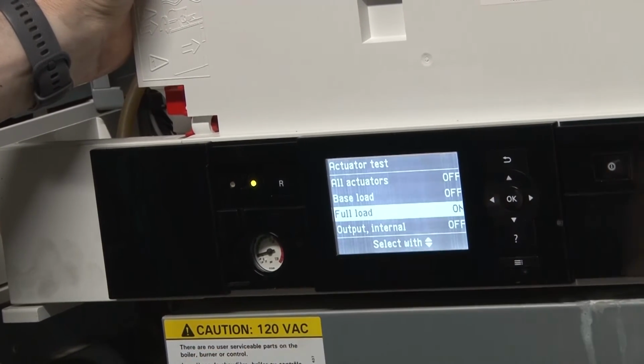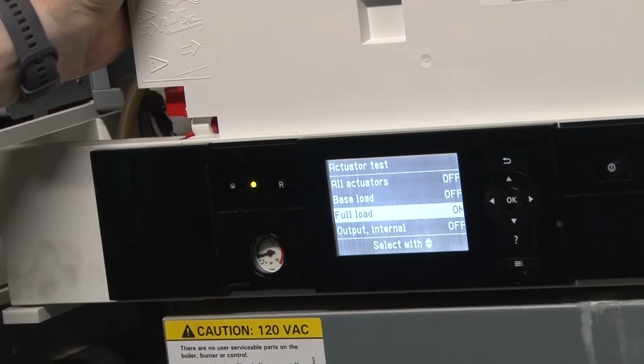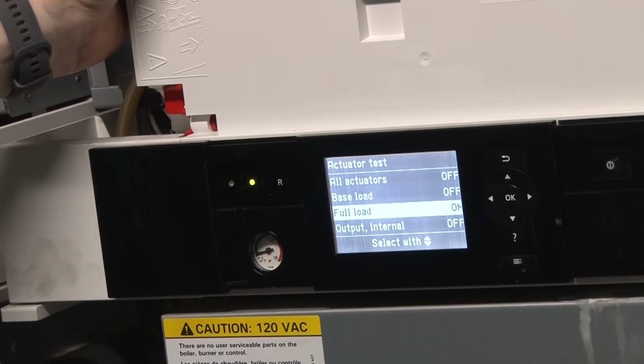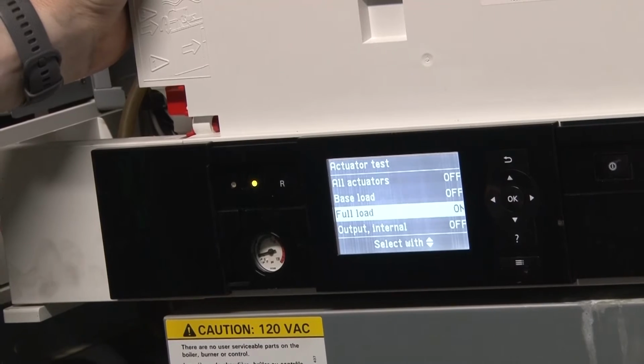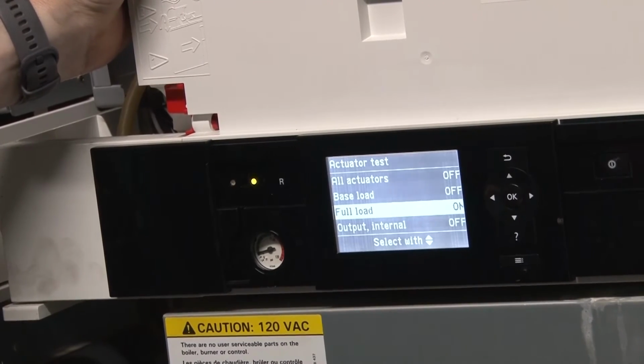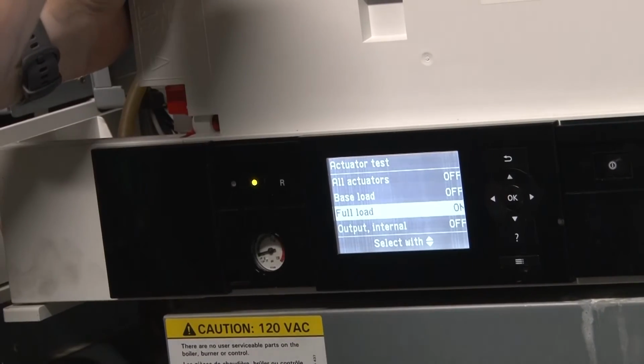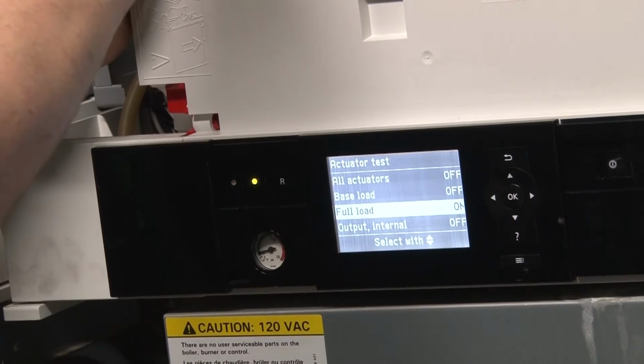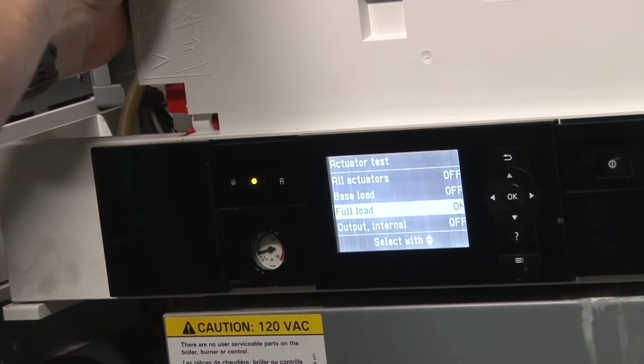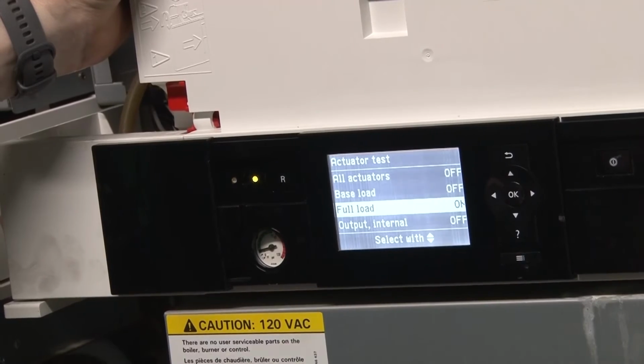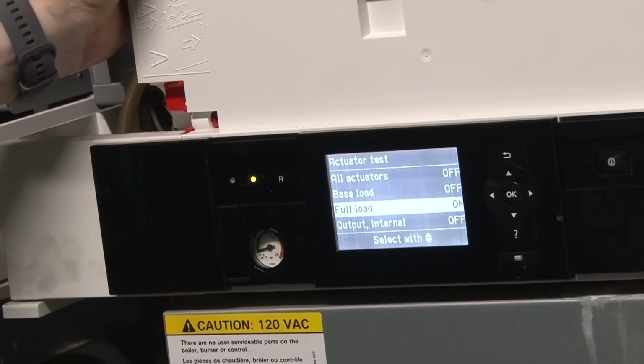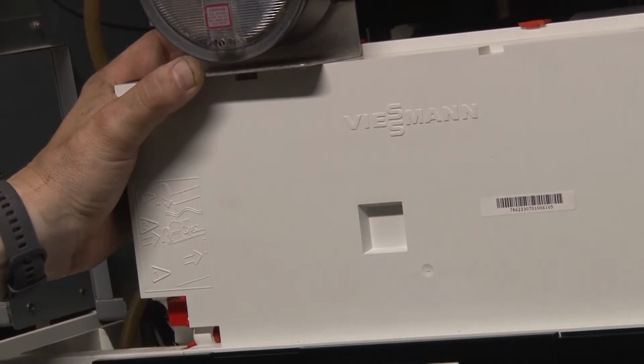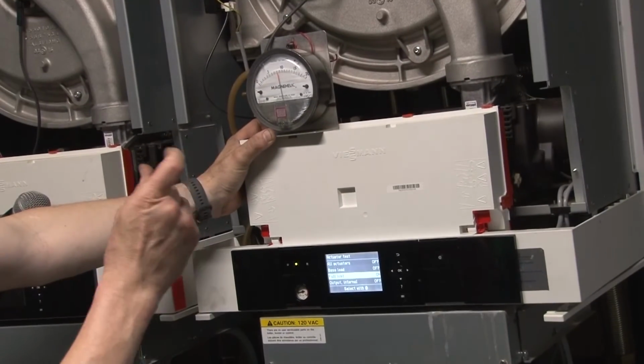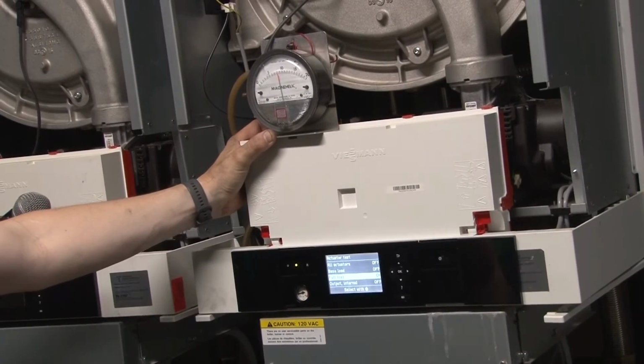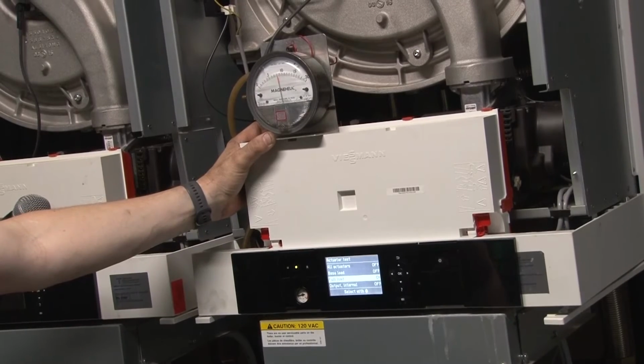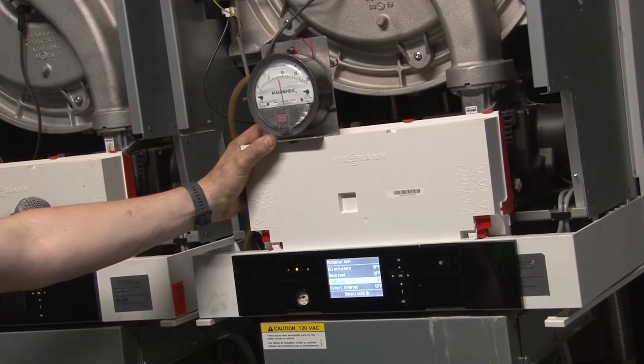And full load, if I put in the full load, the boiler's eventually going to go to high fire. So when I'm doing a running gas pressure, we call this running pressure, dynamic pressure. What we're trying to achieve here is the boiler gas pressure on high fire not dropping down below that 4-inch critical mark for natural gas. If it was propane, we can't drop below 10 inches of gas pressure on high fire. So your tolerances are even tighter if you're on a propane system. So it would be between 14 and 10 inches for propane, natural gas between 4 and 14 inches here.